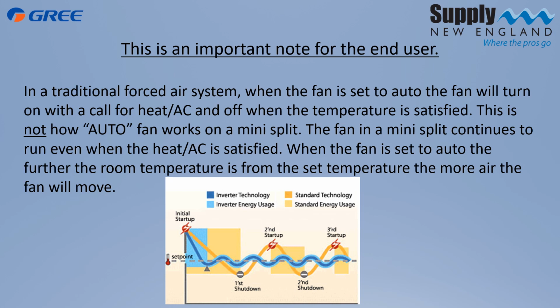And there's a couple of reasons for that. One is we want to keep that air circulating to make sure the temperature is even throughout the room. And the second is that there is a thermistor on the unit that is actually sensing the temperature, and that is what is controlling when the system comes on and off. That's why we have the fan. And what's going to happen here is as the temperature is further away from our set temperature, the fan will speed up, and so will the outdoor unit. As the temperature gets closer to our set temperature, the fan will slow down, and so will the outdoor unit. Part of the modulation, and that's how it works.